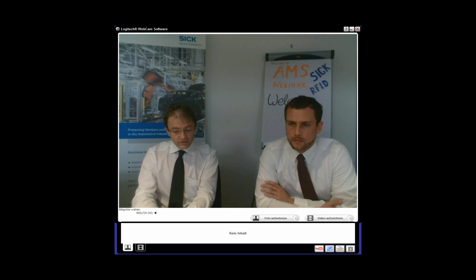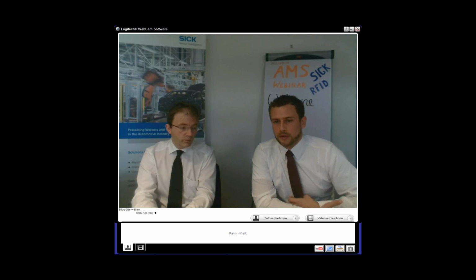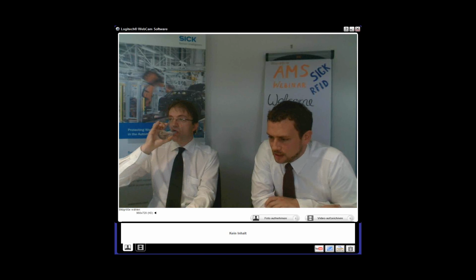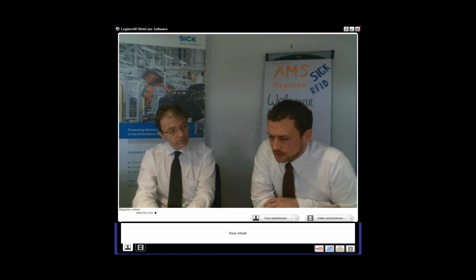Yeah, as said before, a standard temperature cycle is 20-30 minutes, 200 to 230 degrees, something like that. That's where we focused on our testing. We have a test result from one user who left the label inside the oven for, I think, a complete night at 180 degrees, and the data arrived here. But that's something we can't guarantee. That's what we have seen. So the specification basically is 230 degrees for several cycles of 30 minutes. This is the specification that we give with the transponder. From our testing experience, the transponder can withstand higher temperatures as well as longer duration. But from our side, we need to stick to the data sheet. This is what we can make sure reliably works.